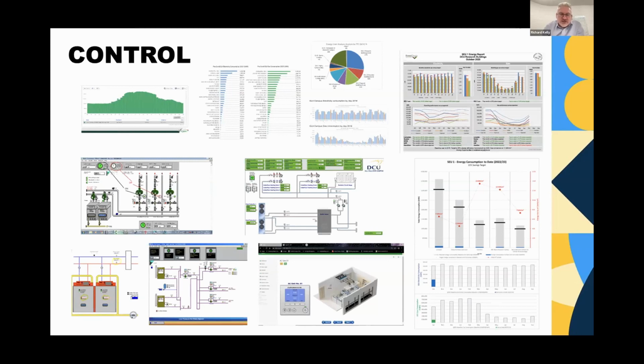We have a building management system - there are a few graphics you can see there. Every system that uses energy in DCU is on our building management system, and we can control whether it's a boiler, an air handling unit, a chiller, a heat pump, plus all the ancillaries like pumps, fans, and valves. We can control them all from our building management system, and by doing that we can interrogate problems but also drive energy down little by little.